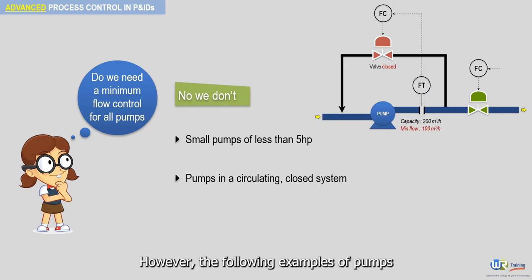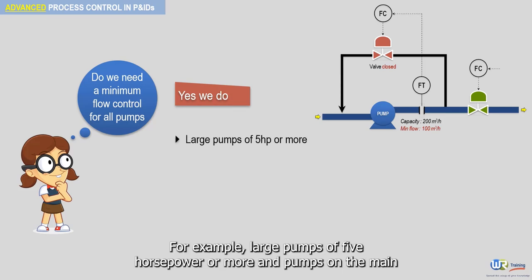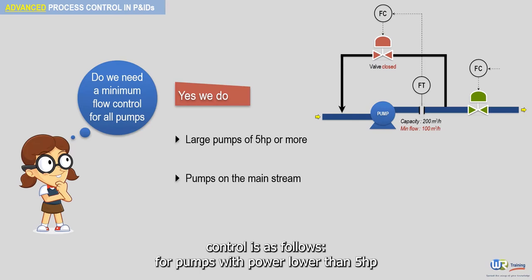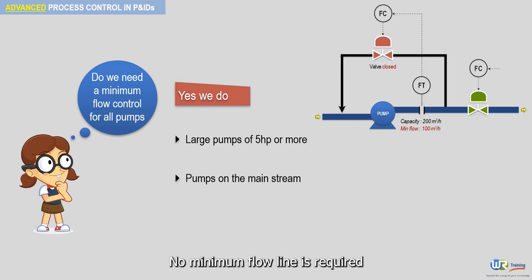The following examples of pumps may require minimum flow control: large pumps of 5 horsepower or more and pumps on the mainstream. The rule of thumb for providing minimum flow control is as follows: for pumps with power lower than 5 horsepower, no minimum flow line is required.